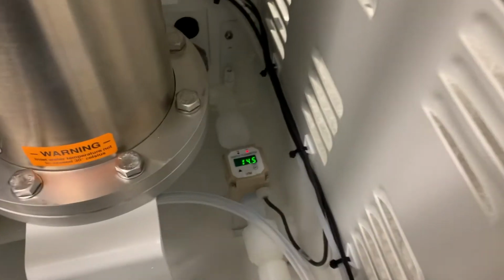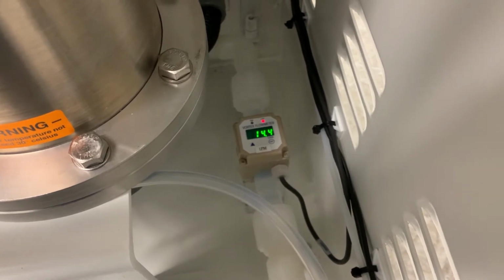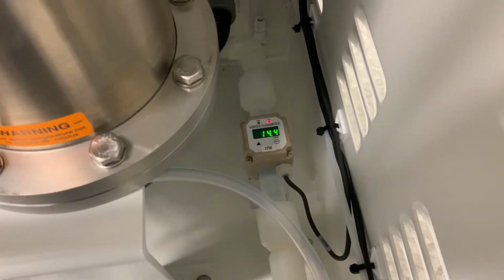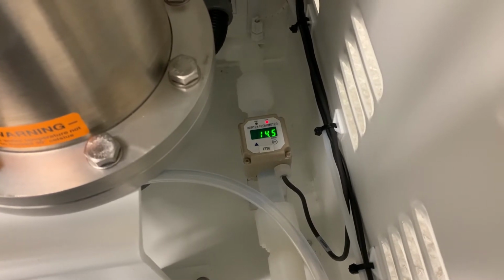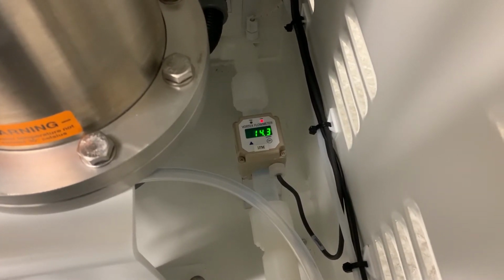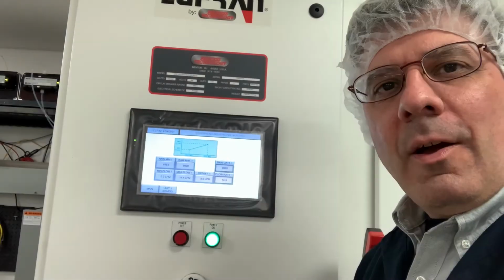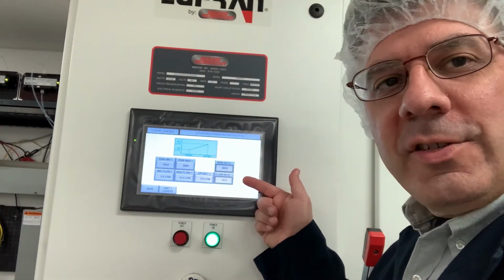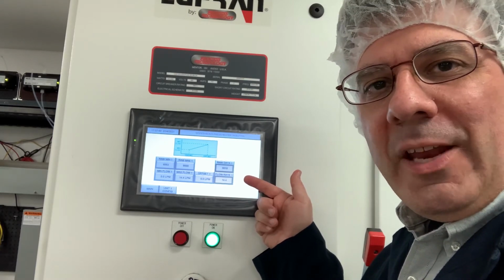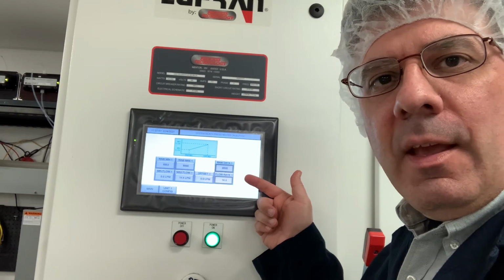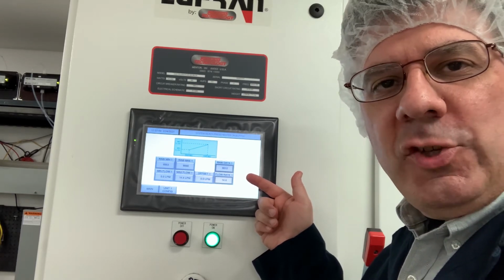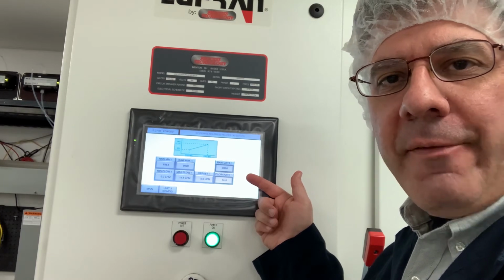Now, the first step is to establish your highest operating flow rate. For that, we do this on the back of the unit and observe the flow meter. So you'll need to open up the back door. All right, the value back here is 14.3, 14.4. That's pretty close. Let's go back to the front. Okay, we're back at the front. The value here is 14.3, very close to the flow meter on the other side. We're probably good. If your readings are within about 0.2 liters per minute of each other, consider that close enough.